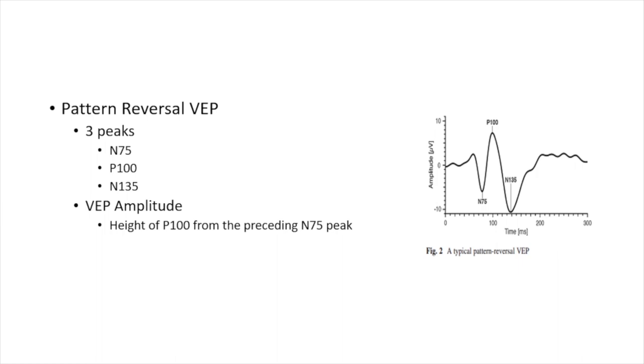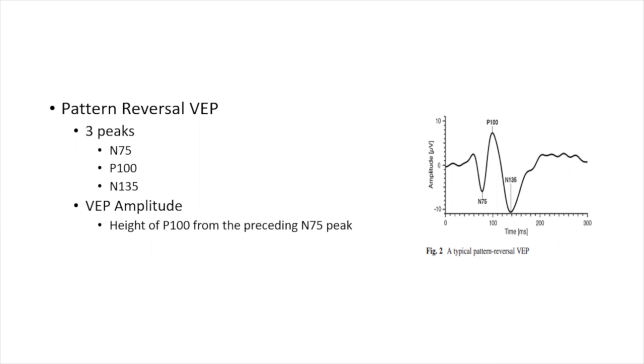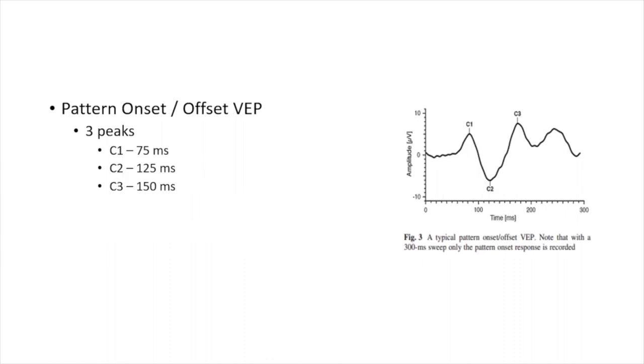The amplitude of the P100 wavelet is measured from the maximum peak to the trough. For pattern onset/offset VEP, instead of the negative-positive-negative sequence seen in pattern reversal, we see a positive-negative-positive sequence — almost the mirror image. To avoid confusion, the nomenclature changes from N/P to C1, C2, C3. On average, C1 comes around 75ms, C2 around 125ms, and C3 around 150ms from stimulus onset.